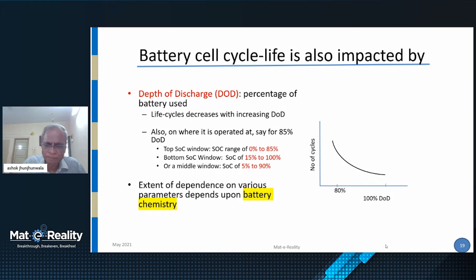As I told you, depth of discharge matters. If you put 100% depth of discharge, the number of cycles goes down. If you put 80%, the number of cycles goes up significantly. It also depends on whether you use the top window, bottom window, or middle window — I'm not going to get into that. Best is between 5 to 85%, or 10 and 80%.